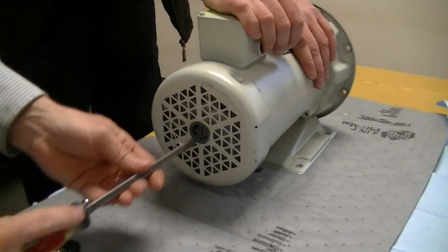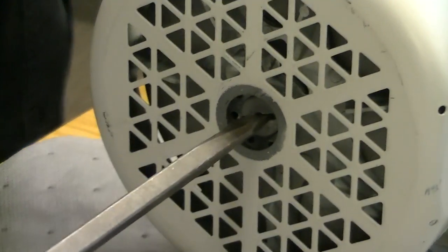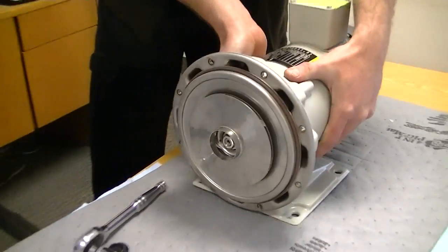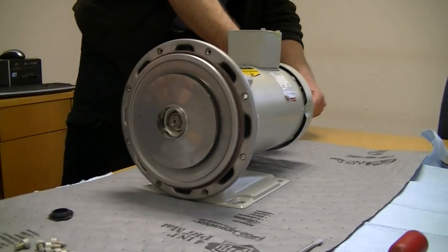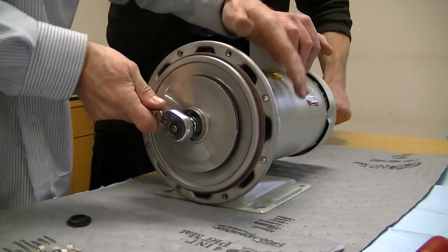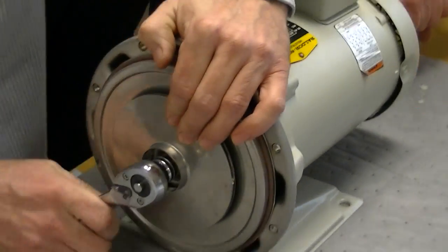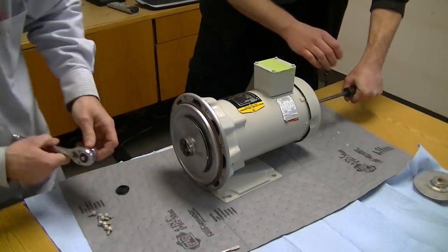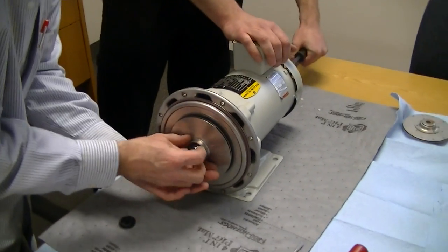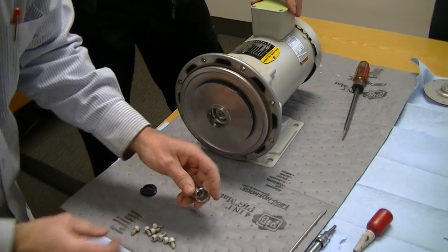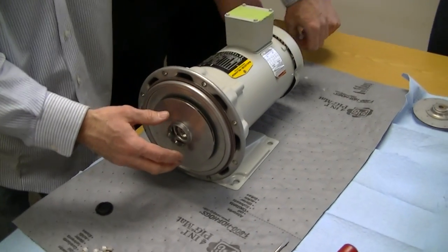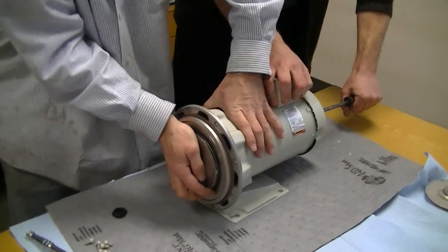We're going to hold that with a screwdriver to loosen the impeller. So you hold that, and then you're going to take your 5/8 wrench and you're going to loosen this impeller. There's a nut on here that's coming right off. You take this nut off because the shaft of the motor is threaded.